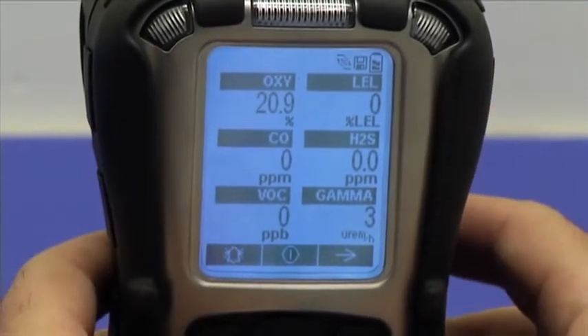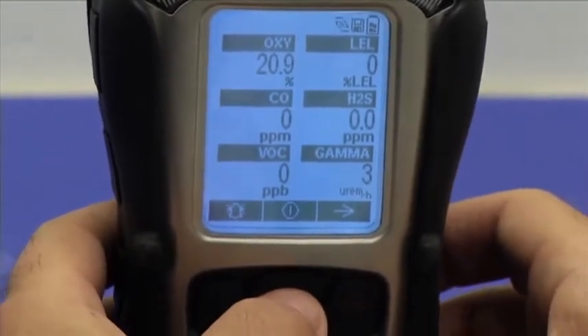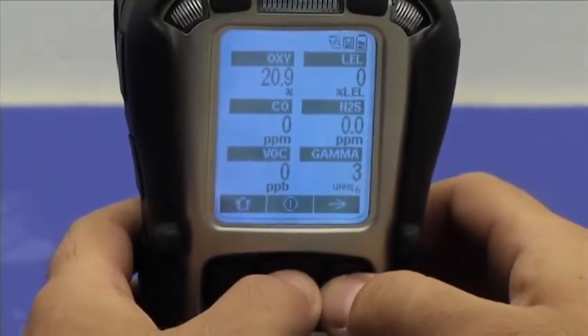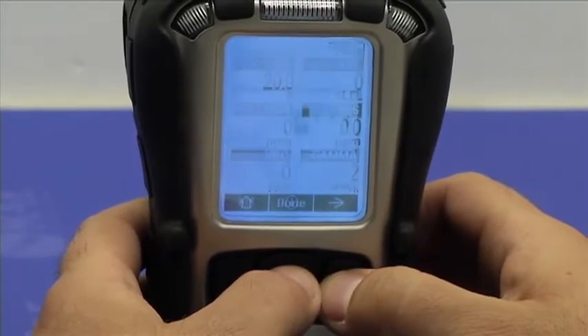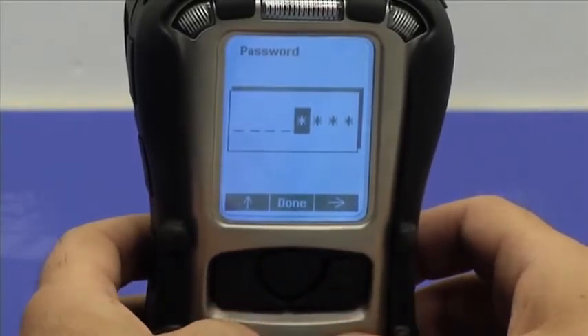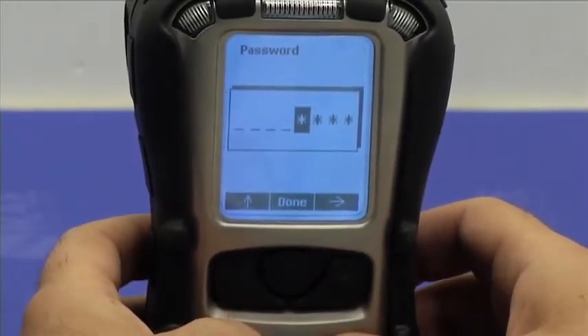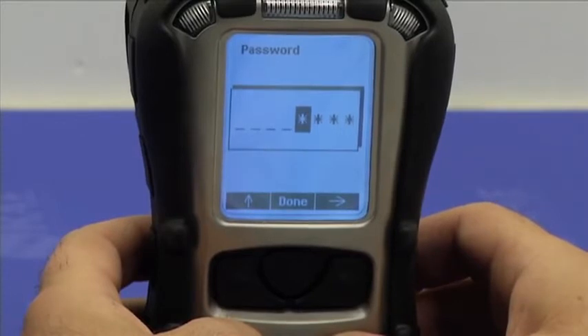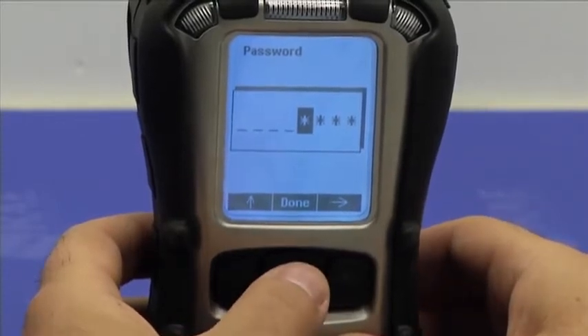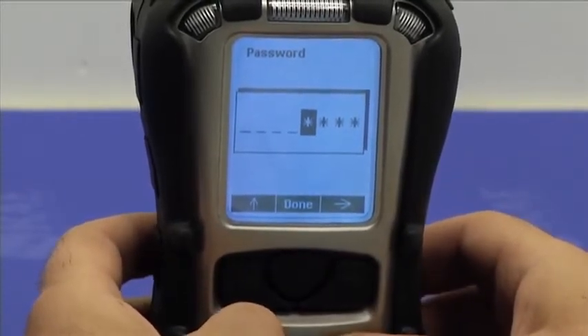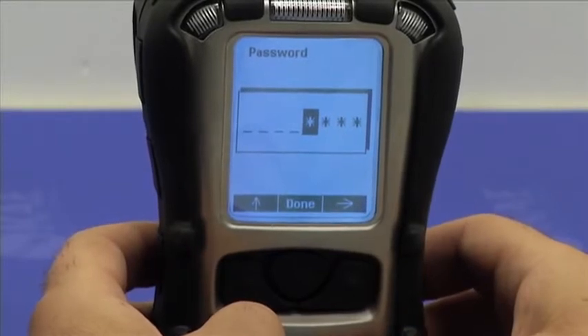To do so, I have to simultaneously press and hold the Mode button and the N button until the password screen appears. If a user does not know the password, basic calibration-related tasks can still be performed. If I don't know the password, I would press the Mode button, and I will be taken to the basic calibration menu.